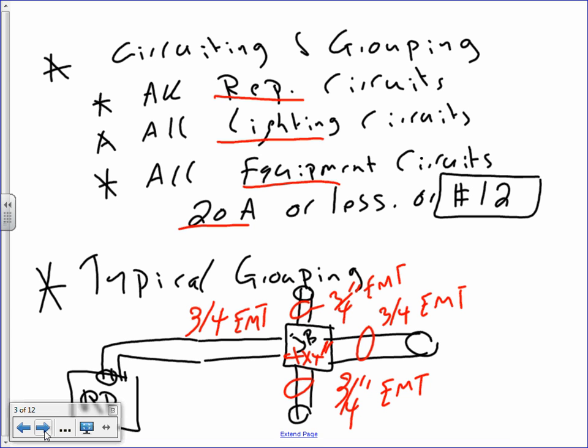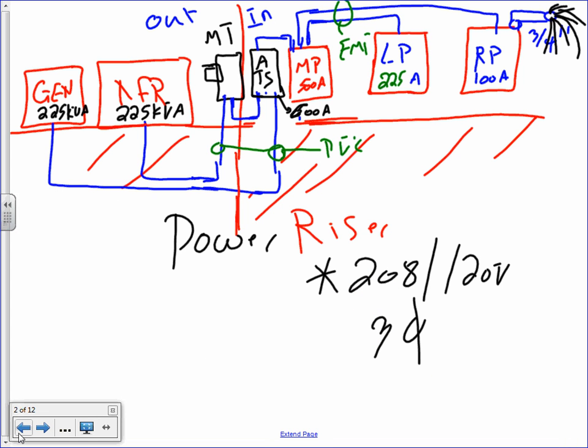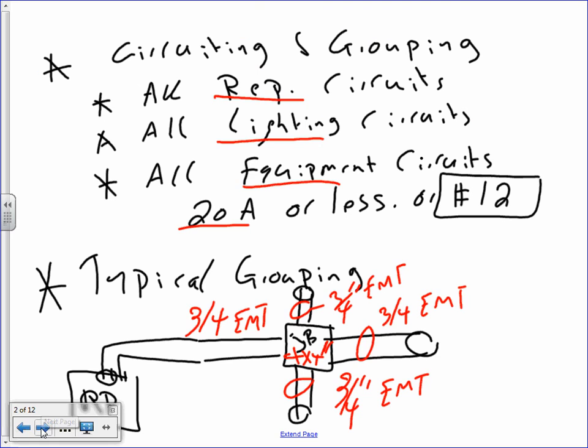When you take circuits to feed receptacles, the best way in conduits is to group them, right? You group them in a conduit: all your lighting circuits, all equipment circuits of 20 amp or less, which take number 12. Can everybody understand what I mean here? If you have receptacles to feed from a receptacle panel, the best way to do it is to come over here, take 3/4 of an inch from the panel with as many conductors as you can fit in the 3/4 of an inch, and go there and feed all the receptacle circuits.